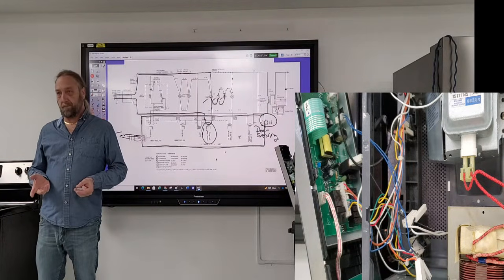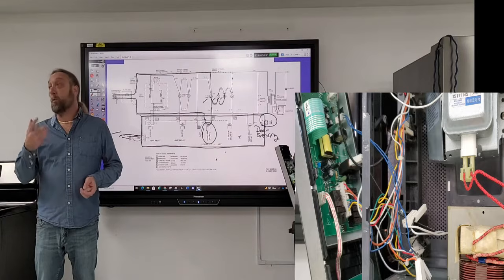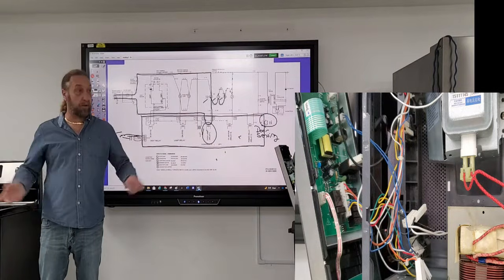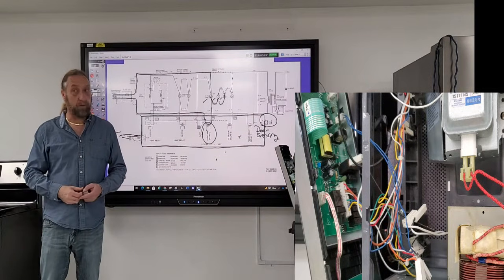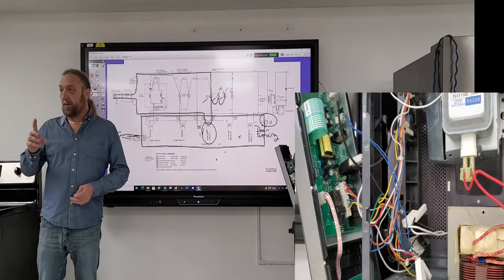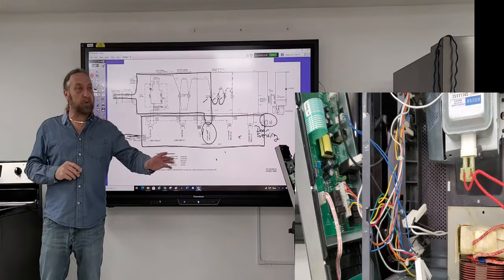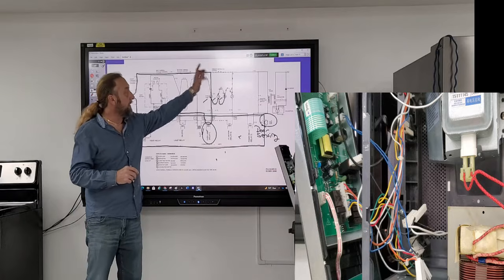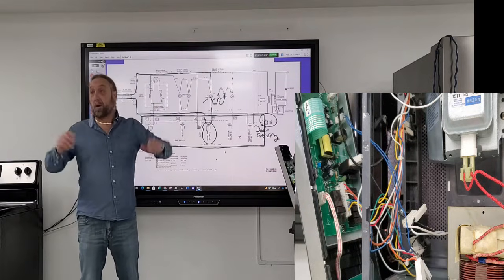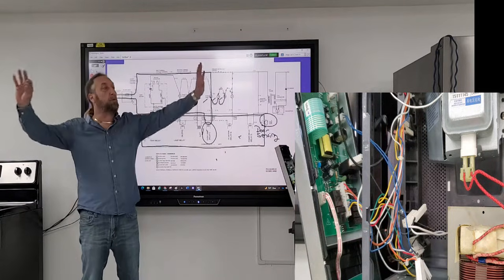It just won't blow the fuse if there's an issue. It won't act as a safety device if the other switches fail to do their job. It's a failsafe. So let's explain though — if the primary switch is bad, this one, it'll run, the light will come on, it'll start counting down, but no fans or nothing.